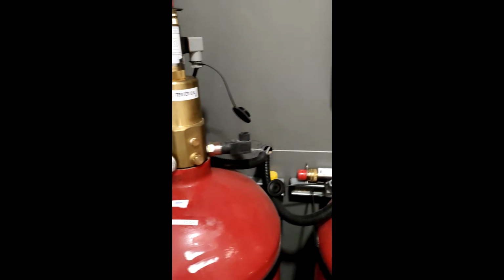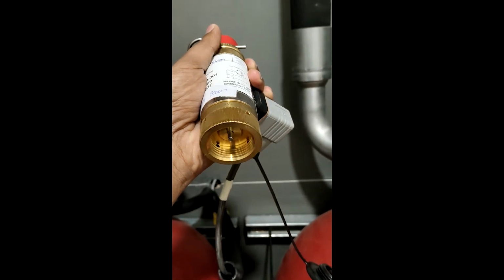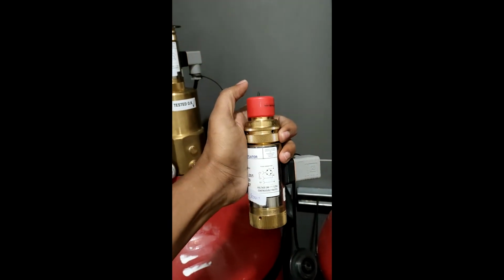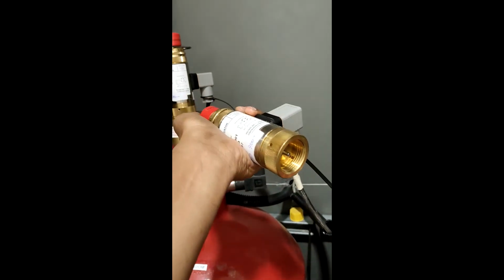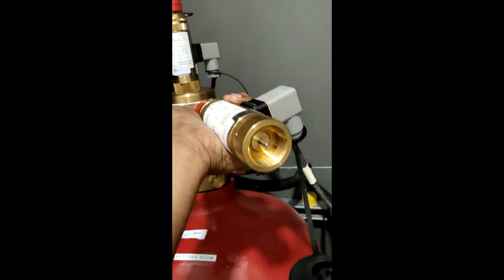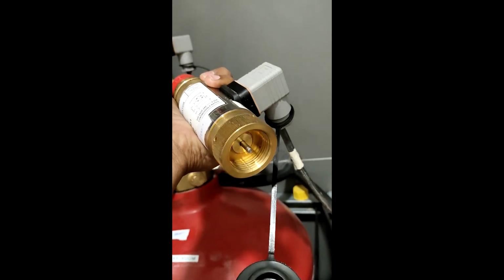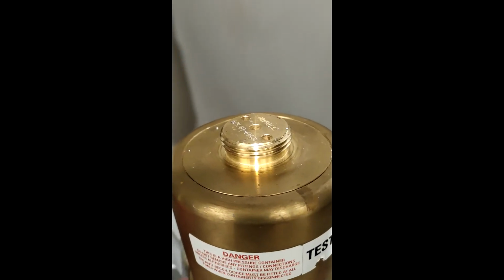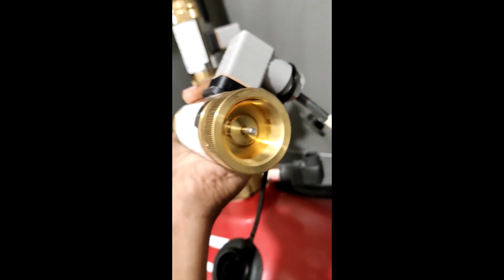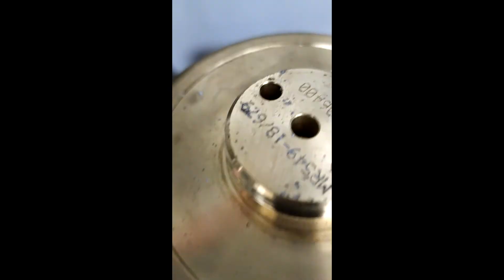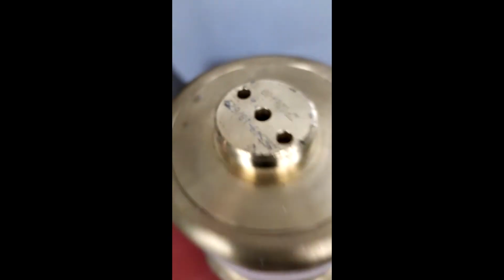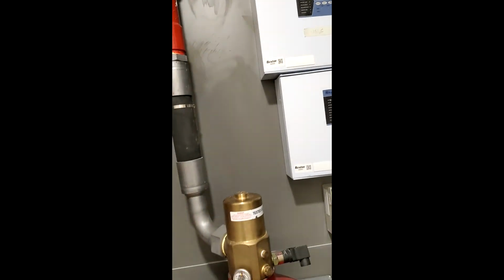Okay, for example, I will show how this actuator looks. See, this actuator is currently in normal condition. Let me open this safety pin. Okay, so now I have opened the safety pin. Let me just check. I'm just going to push this button. See, it gets activated. This is how it works, and here we are going to connect the actuator. This particular pin goes inside this hole, so that it will pass the information to the cylinder to release the gas. So this is how the Novec system will work.